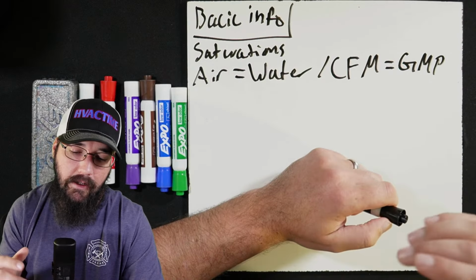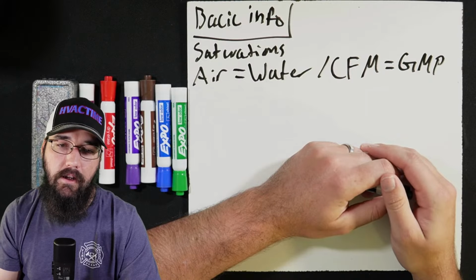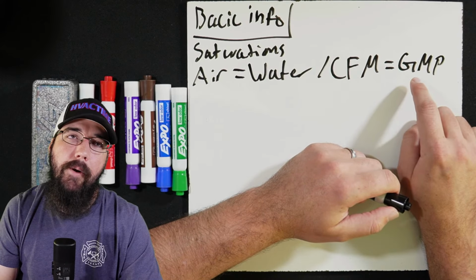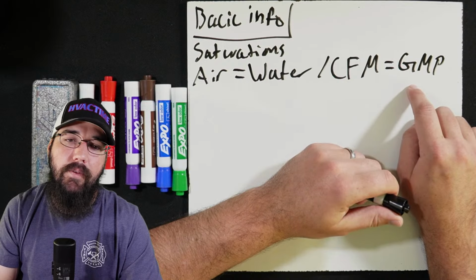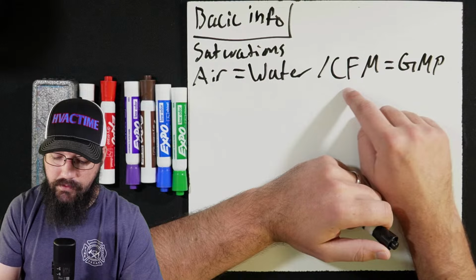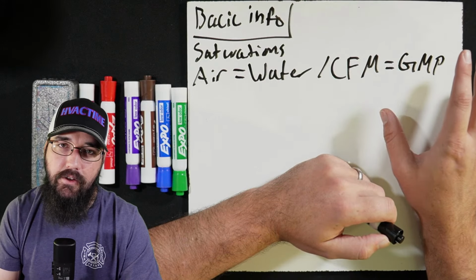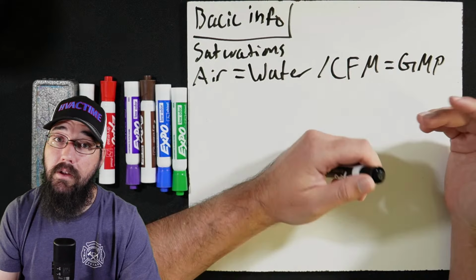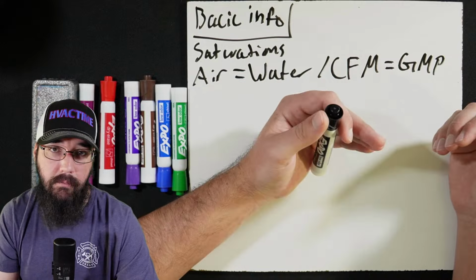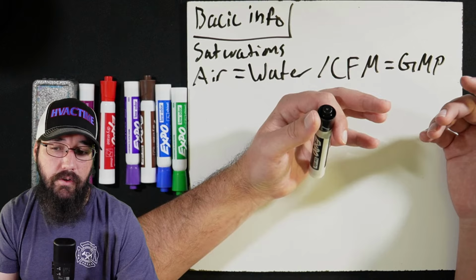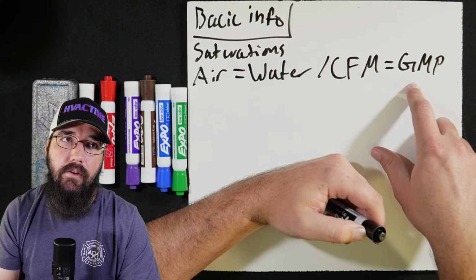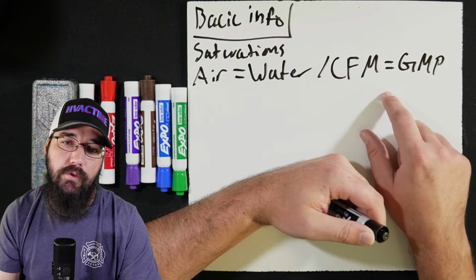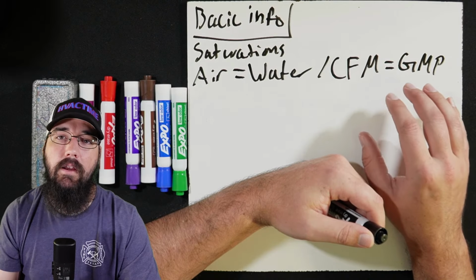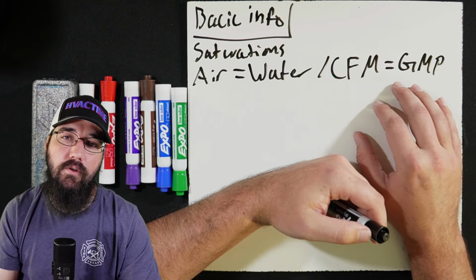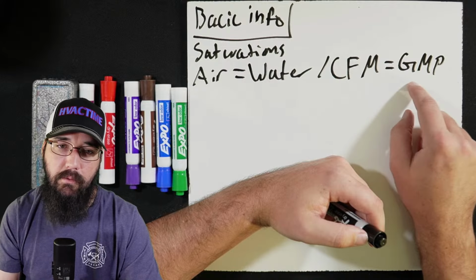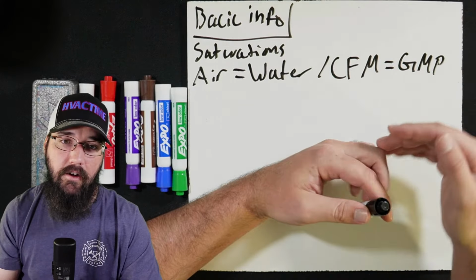Now, something that I sometimes overlook, or I don't specifically call it out, just because this is a simple way to think of this. What does get more complicated and what does change is the machine itself, is the control system. If you're not used to working on heavy equipment, we're talking large commercial RTUs as an example, then you may not be familiar with these controls that are in chiller systems. That's going to make it that you're going to have more struggle with the controls aspect of this than you probably will with this. But if you can get this in your head, you've just taken another step forward.